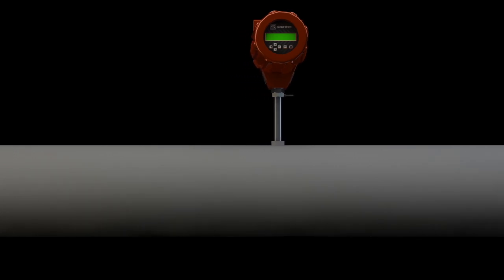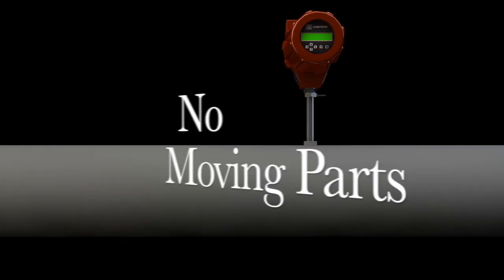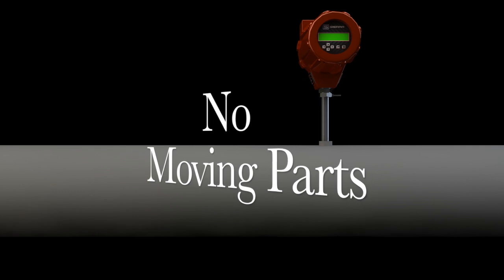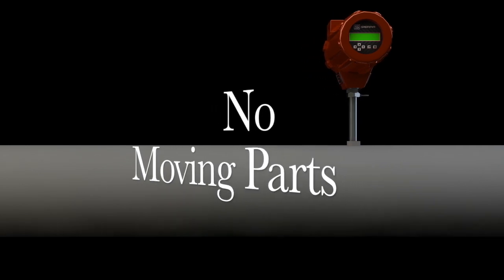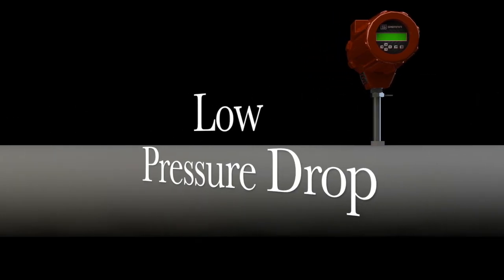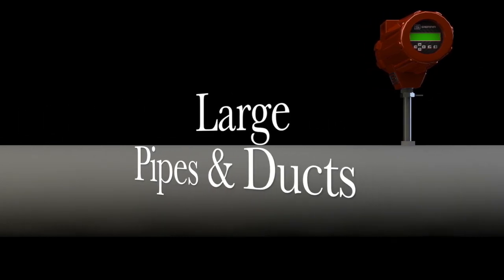Since they are rugged and reliable, have no moving parts, are easy to insert via hot tap, have negligible pressure drop, and offer an economical solution to large diameter pipes and ducts, thermal technology has been rapidly adopted over the last decade.